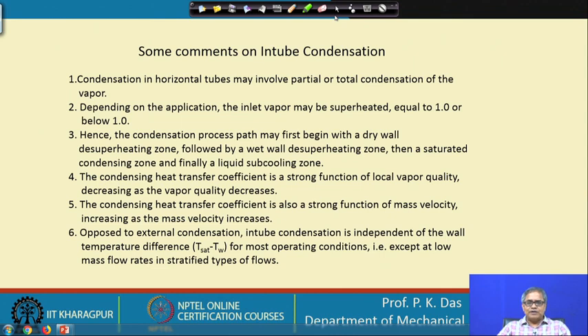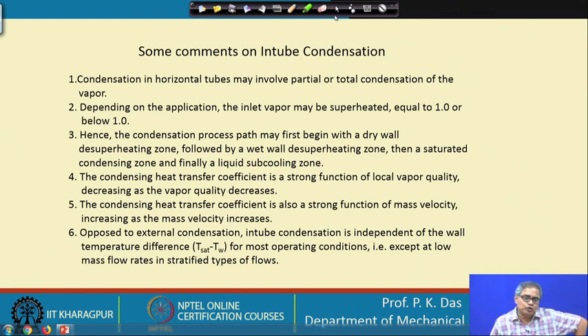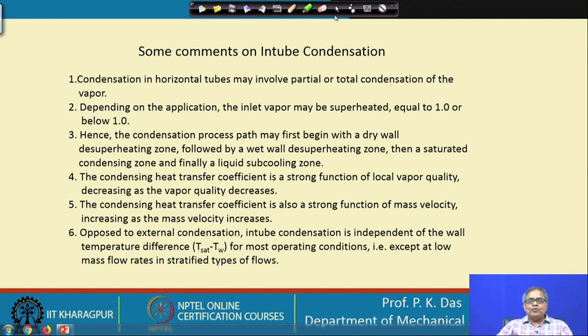This represents a major challenge for a heat exchanger designer. Such designs are quite challenging and cannot be done without iteration. For a particular duty we calculate the de-superheating zone, the two-phase zone, and the sub-cooling zone, but when the duty or heat load changes, these zones shift. In many cases, extra capacity is provided in the condenser to accommodate this. If the design is too tight, it will be sufficient only for one specific operating condition.